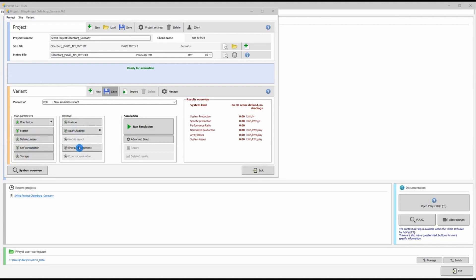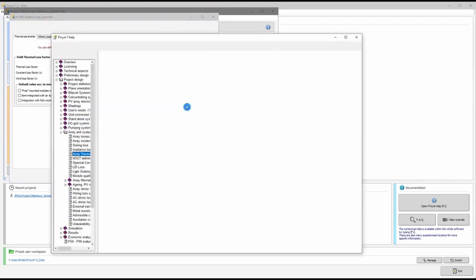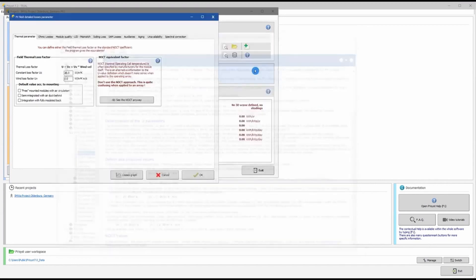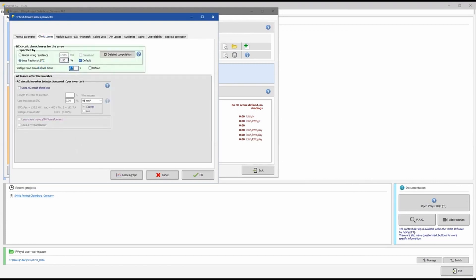Let's adjust the detailed losses. Clicking the Detailed Losses tab opens its dialog box. I'll go through all parameters — click the question mark if you need help. My ground-mounted system is a free-mounted system with air circulation behind the panels, so I select that option. For ohmic losses, I keep the default 1.5% DC loss.